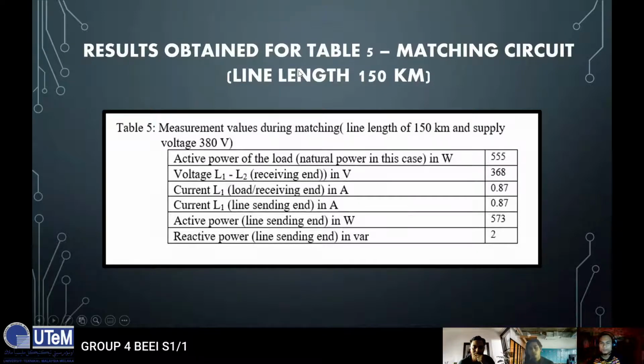Okay, for the result we obtain for table 5, matching rig circuit, line length 150 km. Active power of load is 555 watt. Voltage L1 to L2 at the receiving end is 368 volt. For current L1 at the receiving end is 0.87, and for current line 1 at the sending end is 0.87, and active power at the sending end is 573. For the reactive power is 2 var.